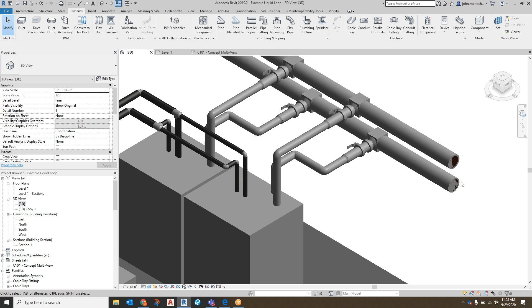So this is a CDU example - this is the secondary loop, this is the primary loop. These are, I believe, 2.5-inch connections and 3-inch connections on the cooling or chilled water side, but they look a lot bigger because they're insulated. So users might think they have enough space, but when they actually insulate and run something under the floor, especially under the floor, they can run out of space pretty easily. So one point is we need to give users knowledge of how to tie into these.